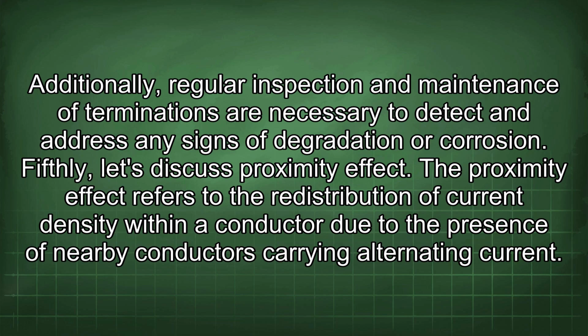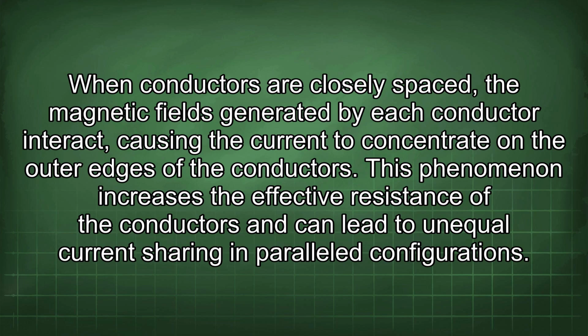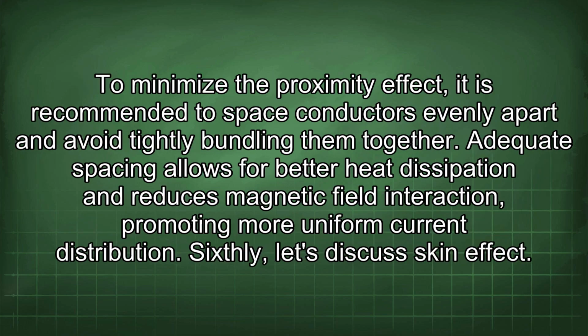Fifthly, let's discuss proximity effect. The proximity effect refers to the redistribution of current density within a conductor due to the presence of nearby conductors carrying alternating current. When conductors are closely spaced, the magnetic fields generated by each conductor interact, causing the current to concentrate on the outer edges of the conductors. This phenomenon increases the effective resistance of the conductors and can lead to unequal current sharing in parallel configurations. To minimize the proximity effect, it is recommended to space conductors evenly apart and avoid tightly bundling them together. Adequate spacing allows for better heat dissipation and reduces magnetic field interaction, promoting more uniform current distribution.